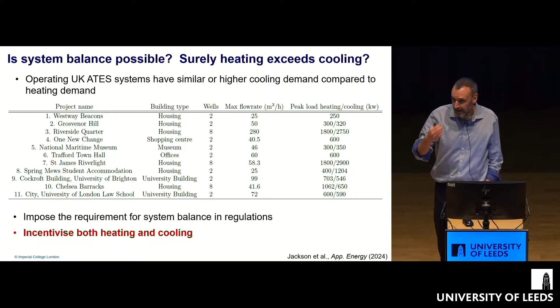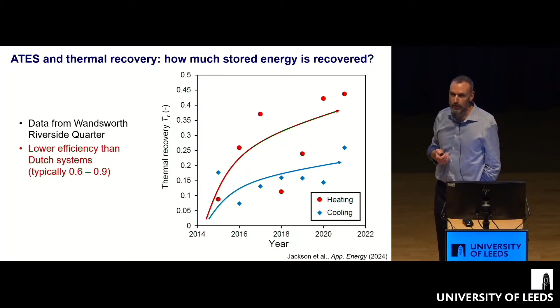Now, not much said about fluid dynamics so far. One thing we're interested in is how efficient the thermal storage is - how much of the stored energy do we get back? We can look at data from the Wandsworth system and define a thermal recovery factor, essentially the fraction of what we store that comes back to the surface. It's actually rather small for the Wandsworth system, much higher in Dutch systems, where they can get 60 to 90% of the stored heat or cool back. So we might want to ask why that is.